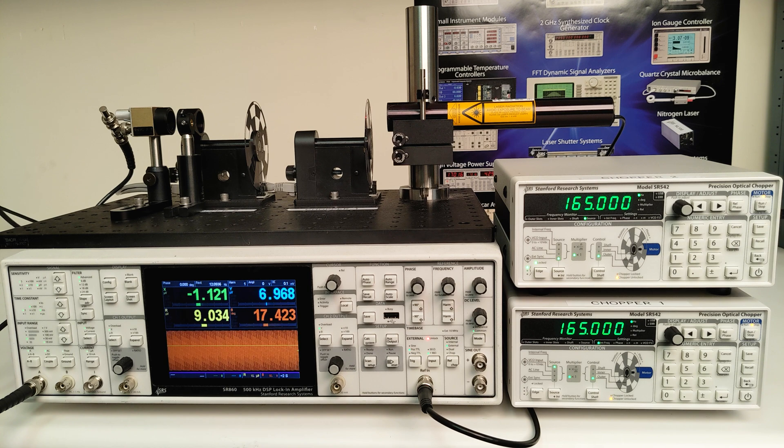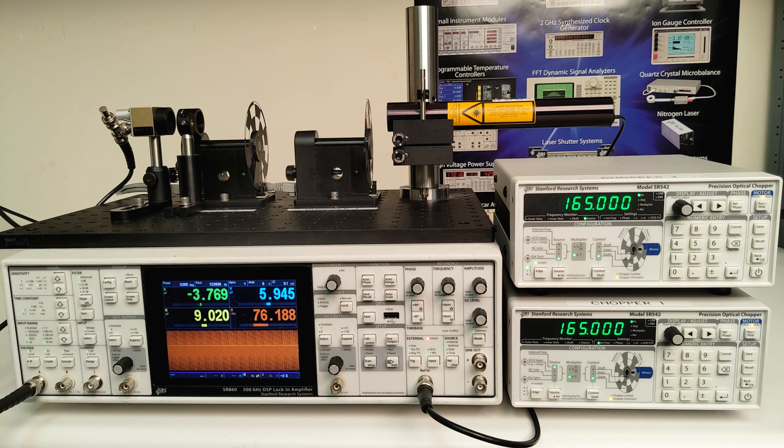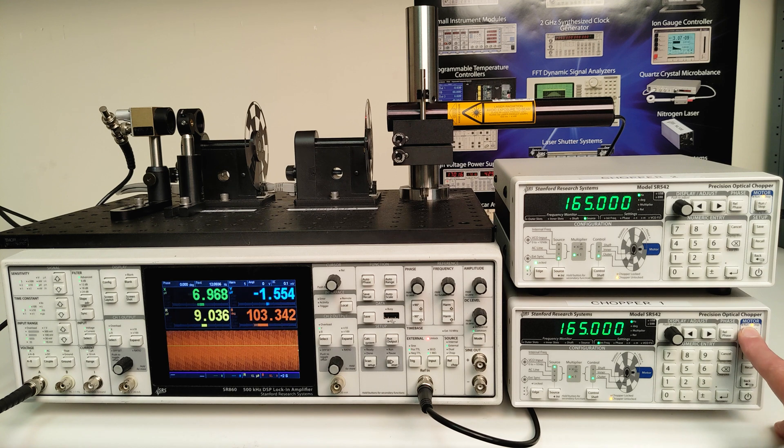The first step towards phase alignment of the choppers is establishing a baseline signal for the 50% duty cycle waveform of a singly chopped beam. This is done by measuring the photodiode output on the lock-in, with only chopper 1 running, and chopper 2 simply acting as a beam pass. I'll start chopper 1's motor.